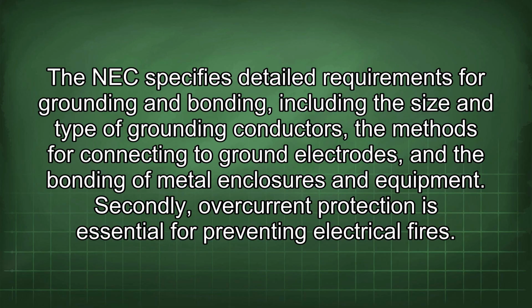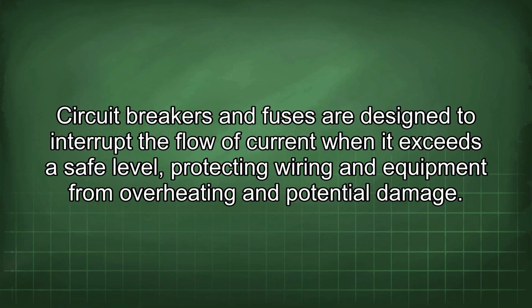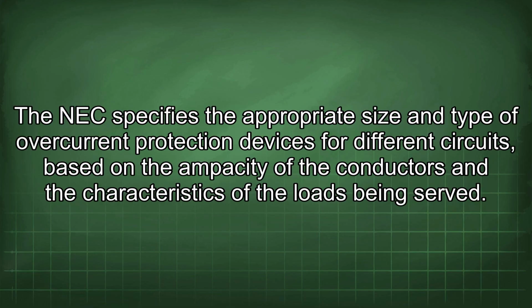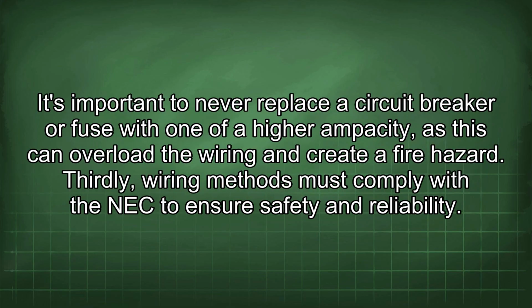Secondly, overcurrent protection is essential for preventing electrical fires. Circuit breakers and fuses are designed to interrupt the flow of current when it exceeds a safe level, protecting wiring and equipment from overheating and potential damage. The NEC specifies the appropriate size and type of overcurrent protection devices for different circuits, based on the ampacity of the conductors and the characteristics of the loads being served. It's important to never replace a circuit breaker or fuse with one of a higher ampacity, as this can overload the wiring and create a fire hazard.